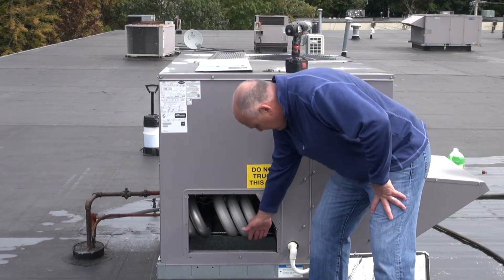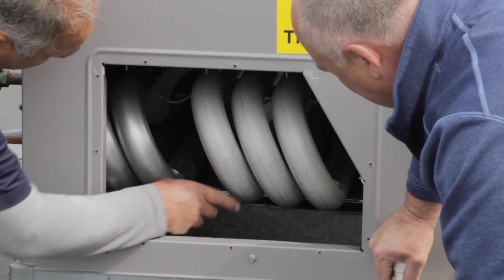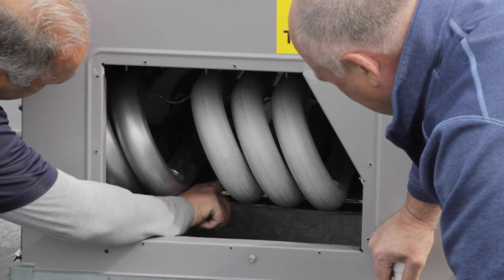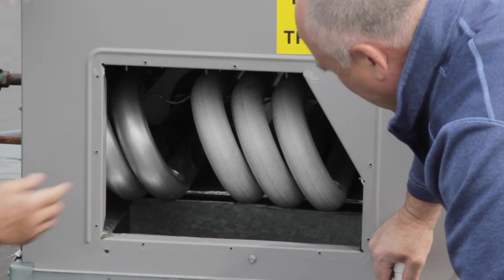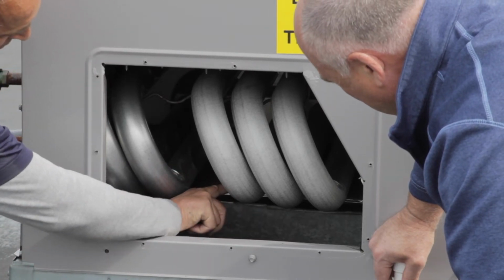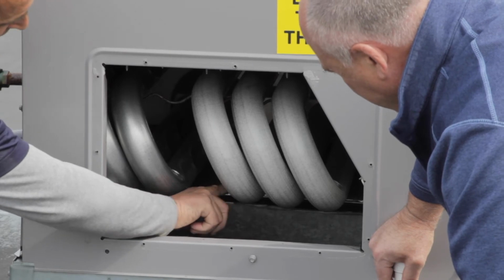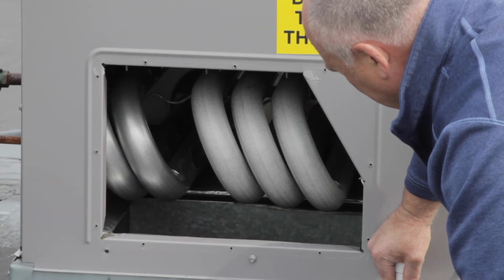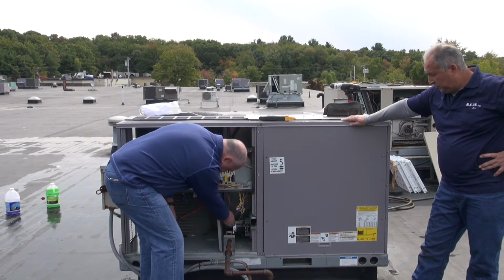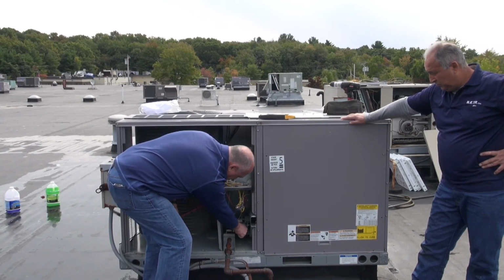In the fall, the heating section is also inspected. The heat exchanger tubes are checked for cracks. If the tubes are cracked, it can release carbon monoxide into the building, so it's important to inspect them regularly. The gas pipe, valves, draft inducer motor, and ignition are also inspected and tested to make sure they're functioning properly.